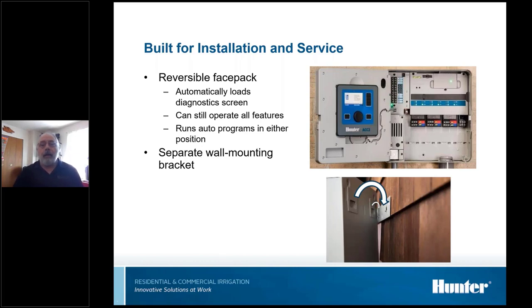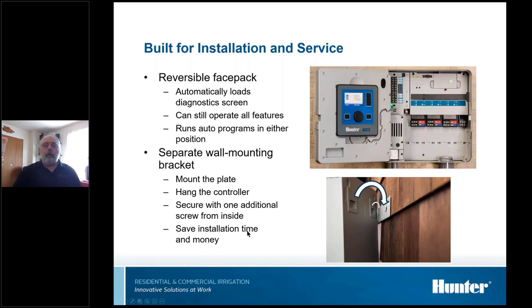The other cool thing, especially on this controller, is that it's extremely heavy. The ACC was also. So putting a wall mount controller this heavy up by yourself is almost impossible. They're so heavy and cumbersome. So what they made was a little bracket, and you just level and mount the bracket to the wall, and the controller just literally hangs on it. Then you mount the plate, hang the controller, and one screw inside the cabinet locks the thing down on the wall. It's way easier, way safer to install this controller.